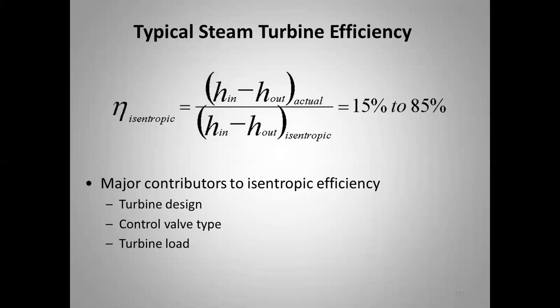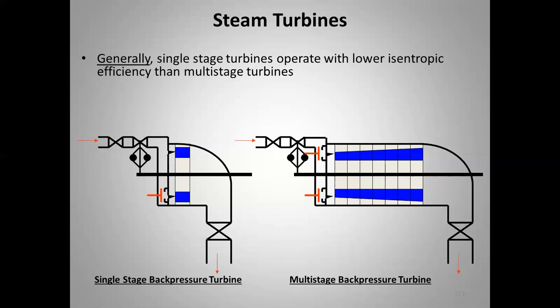The major contributors to isentropic efficiency are turbine design, control valve type, and turbine load. Larger multi-stage backpressure turbines have better efficiency. A small pressure drop or relatively small steam flow rate reduces the number of stages to one or two at most, hurting efficiency. Larger pressure drops and higher steam flows lead to multi-stage backpressure turbines with better isentropic efficiencies.